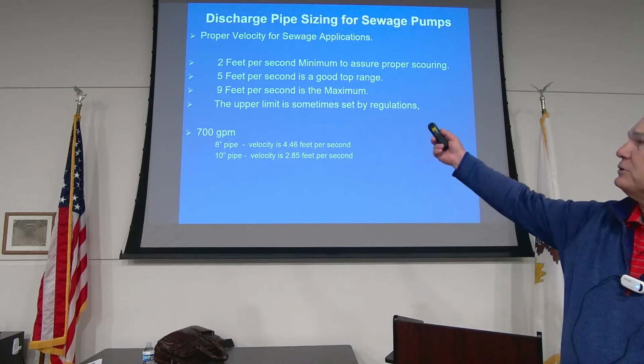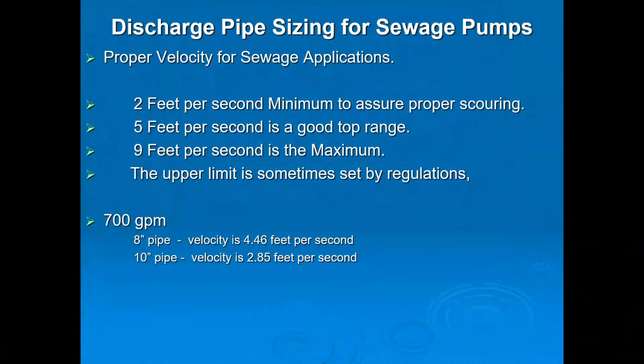So in a station, we look at 2 feet per second in the force main as our minimum design standard when the pump's running. 5 feet per second is the typical maximum. Like I said, we have some engineers who like to go to 9. That's ridiculous, but they like to do it. And we would suggest they not.